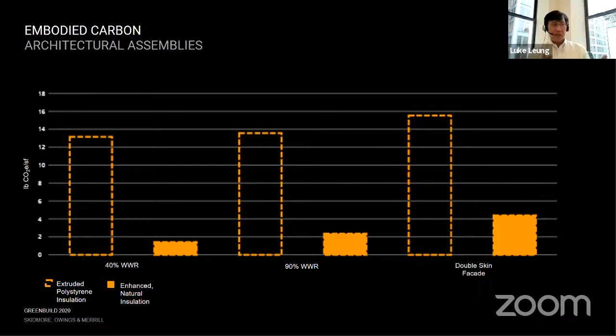But guess what happened? If you start looking at the whole life cycle of the system, the facade and the HVAC system - in this case a VAV system - over a 60 year life cycle, what you'll find out is, yes, the facade is going to consume more embodied carbon, but it reduces the HVAC system size and the energy consumption.